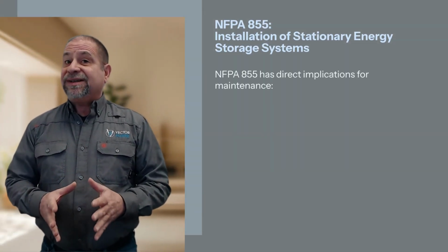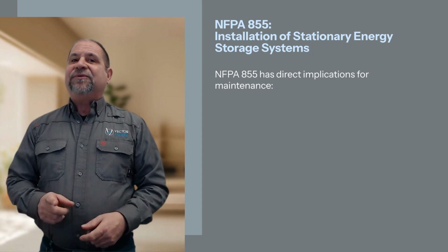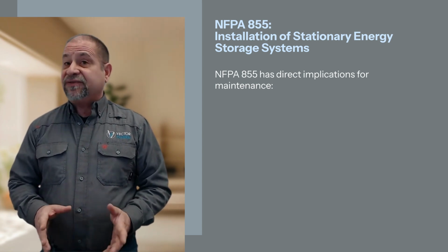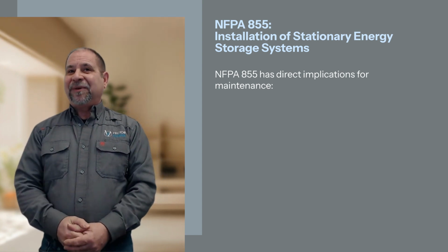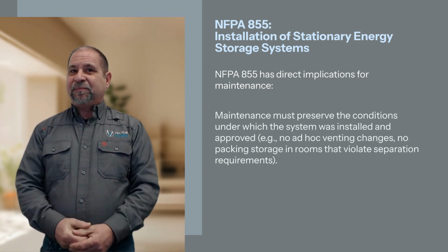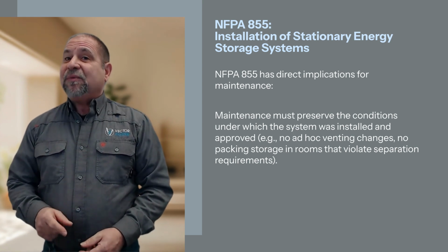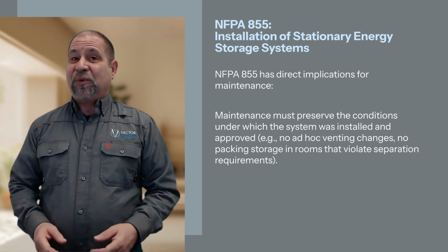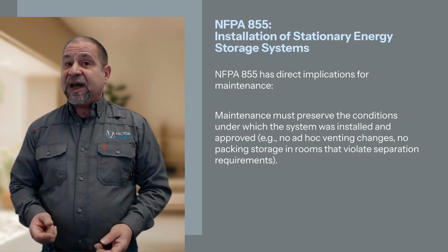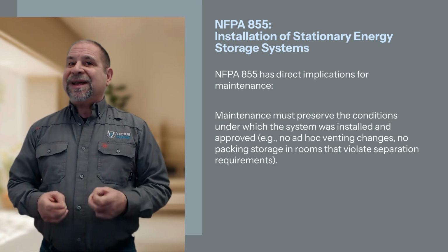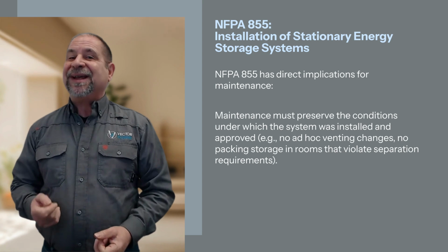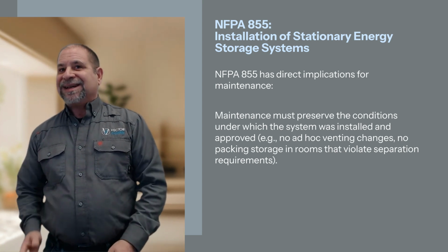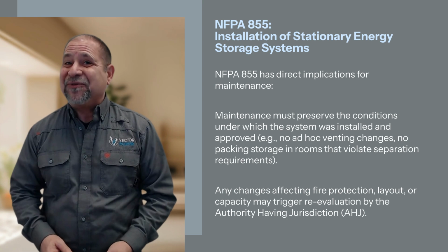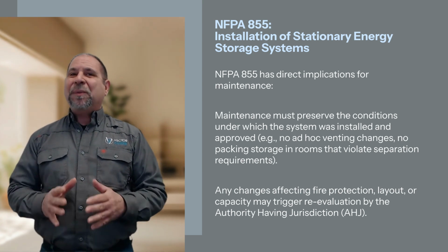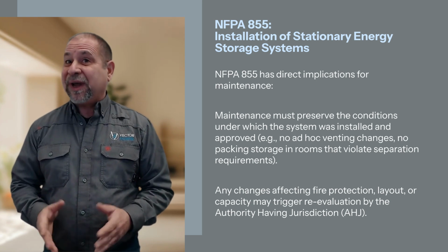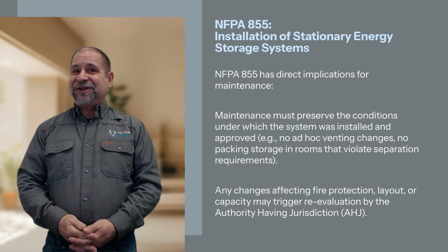While primarily an installation standard, NFPA 855 has direct implications for maintenance. First, maintenance must preserve the conditions under which the system was installed and approved, for example, no ad hoc venting changes, no packing storage in rooms that violate separation requirements. And second, any changes affecting fire protection, layout, or capacity may trigger reevaluation by the authority having jurisdiction.